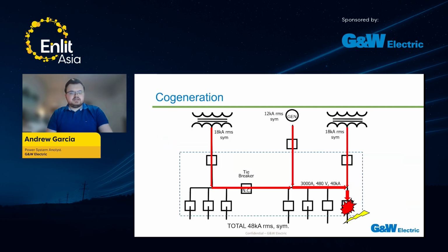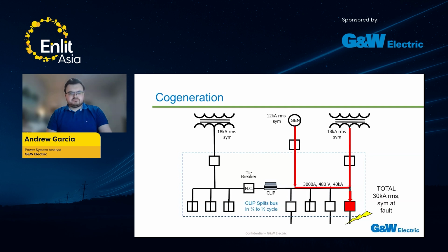Under normal operation, the downstream system is underrated, meaning that equipment could fail and harm any nearby personnel or equipment. With the CLiP installed at that tiebreaker, the CLiP is going to split that bus in 1/4 to 1/2 cycle in a fault, and now your normal system can handle the fault. It's not going to fail, and you are completely safe.